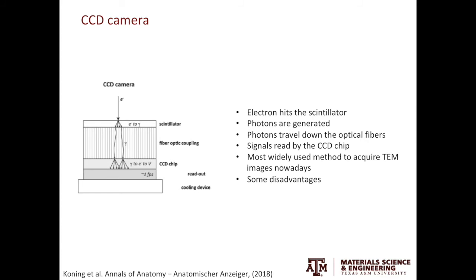Nowadays, CCD cameras are ubiquitous and can be seen on nearly every single TEM. However, there are some disadvantages. In an oversimplified example, when you have an electron beam hitting the scintillator, you have two photons generated and captured by the CCD camera — it's like one pixel getting excited by the electron, but two pixels showing where it's coming from. This degrades the image resolution of your micrograph.